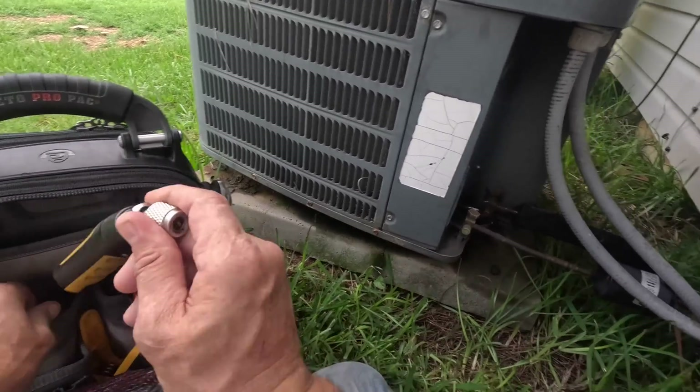It's my blower relay — just my blower relay. No power. To show y'all what I was testing: first I tested on this and got 14-16 amps — that's a wire going to your heat strip. Then I tested on this one that goes from here to your blower relay right here, and I was getting like 15 amps on that one. And if you look down here, that is all burned up. That's because these two wires have melted together, which is causing voltage to backfeed this heat strip. So we are replacing that relay.